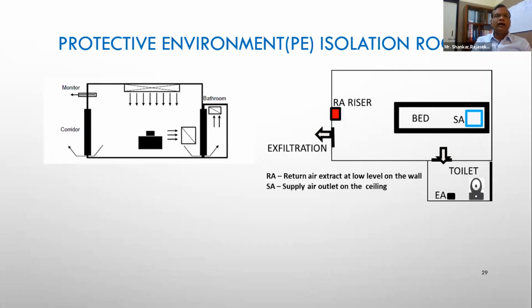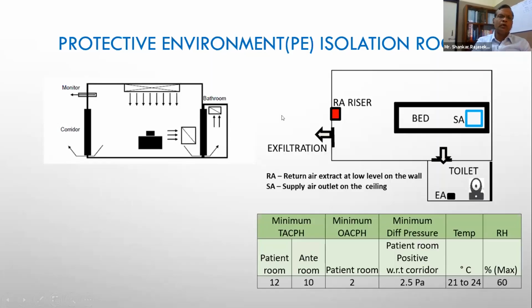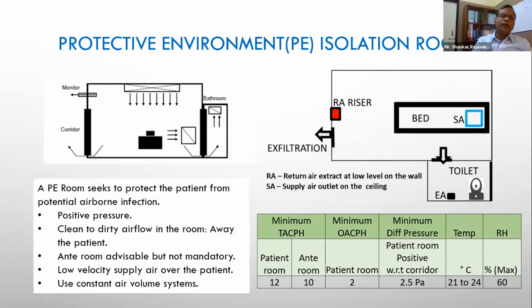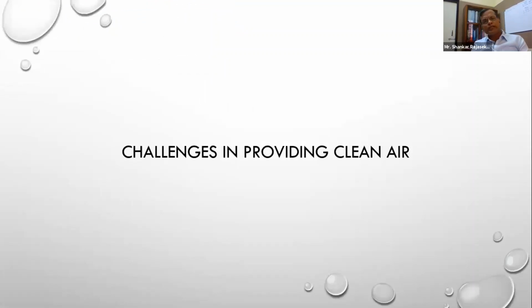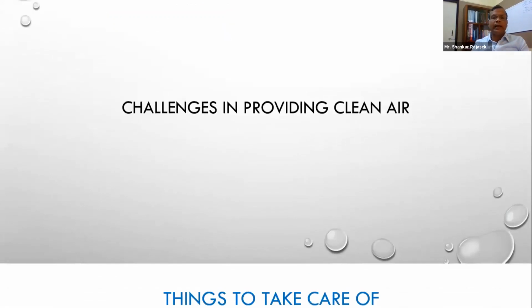So we look at the air being supplied over the patient and the air moving out of the room. This will be a positive pressure room where the patient will be bathed, or washed, by a stream of ultra clean air through HEPA filters, and then it will leave the room so that the patient will be protected from the contaminants from outside. So we look at some challenges in providing clean air now.